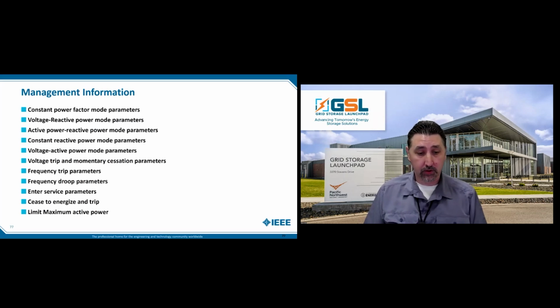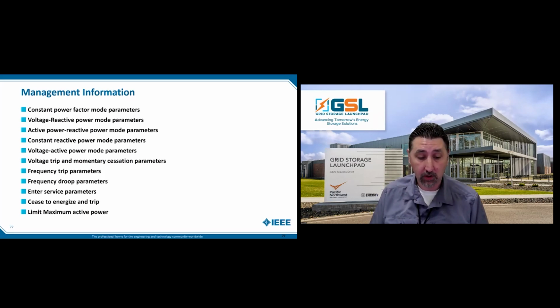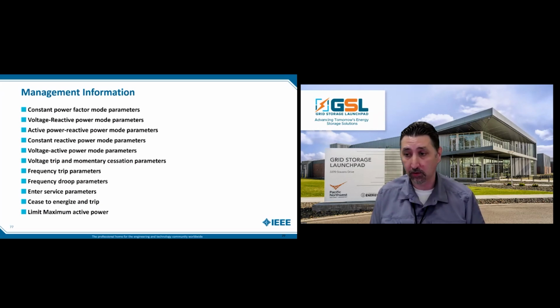Management information includes constant power factor mode parameters, voltage reactive power mode parameters—these are all operating parameters. I won't read through all of these, but some things that might be changed include droop parameters, and depending on how stiff your system is, voltage active power mode parameters. All of these could require changes over time, which is why I usually recommend to industry partners that if you have the option, keep that port connected so you can monitor these things in real time rather than rolling a truck to plug in. It provides value even just for monitoring, but definitely if you have to update those parameters.